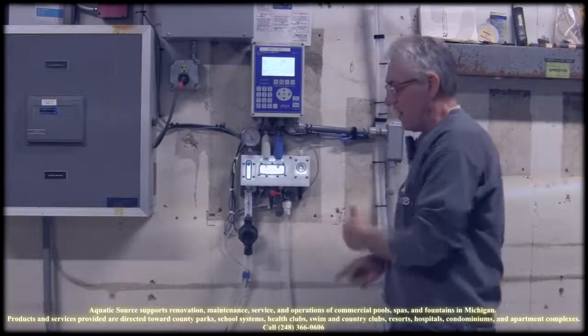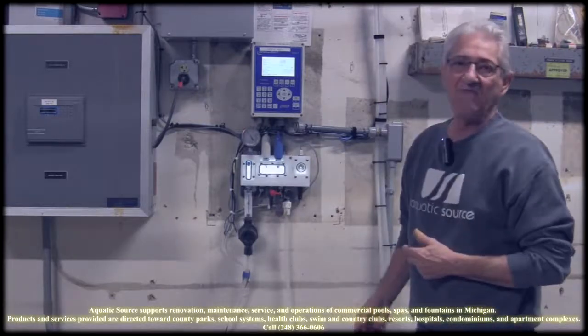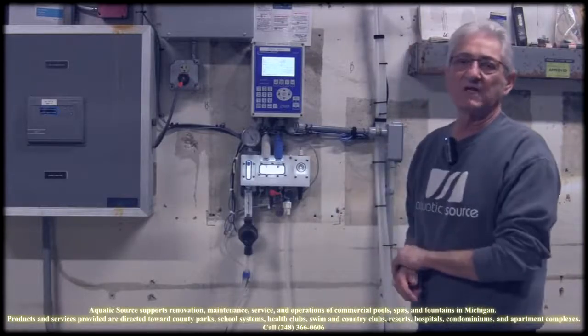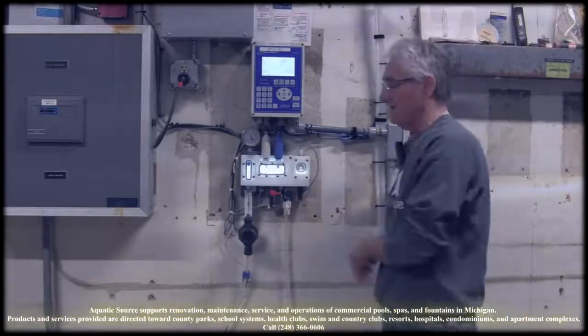Put it back together, let the water flow through it for about a half an hour or so before you put power back on and try to calibrate it, because it will take a while for that solution to clear itself.